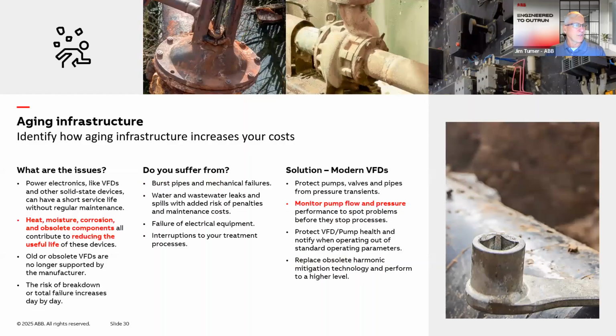One last thing I'll speak of is the larger topic of updating older systems. There's, I'll say, an expected useful life of different classifications of equipment. For example, pumps and motors may have a useful expected life of 20 to maybe 35 years, maybe longer if maintained properly. Electrical switchgear and motor control, maybe 20 to 25 years. VFDs, 12 to 18 years. Computer systems, 6 to 10 years. Your own laptop that you do your work on has its own useful life and obsolescence timeline.